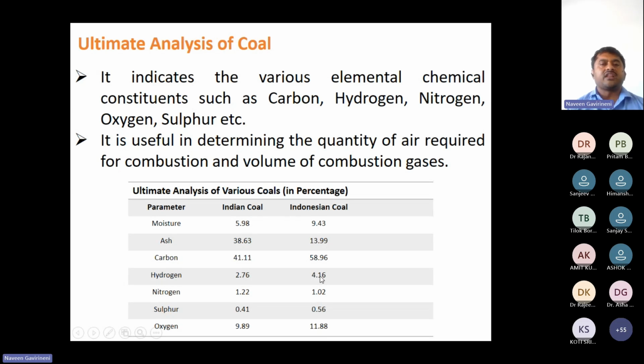So this is the ultimate analysis. As I have explained, from ultimate analysis we get hydrogen, nitrogen, oxygen, and sulfur. Each and every parameter we get, but it will take time. For preliminary analysis, proximate analysis is sufficient for calculation of the direct efficiency. But in detail, we go for the losses method, that means indirect efficiency. That method I will also explain later. There is a determination of air quantity arrangement for combustion and volume of the gas also. So I have compared coal size and coal analysis in our practical industry. Yes, we are using India coal and Indonesia coal. These are the brief analysis from the ultimate analysis.